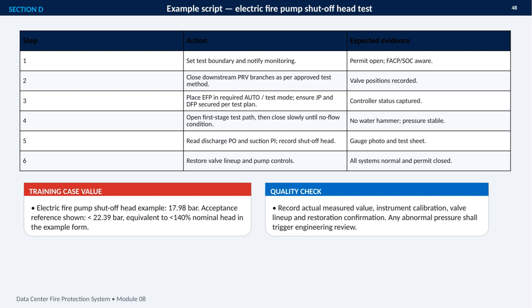The quality check is equally important. Record the measured value, instrument calibration, valve lineup, and restoration confirmation. Any abnormal pressure requires engineering review.